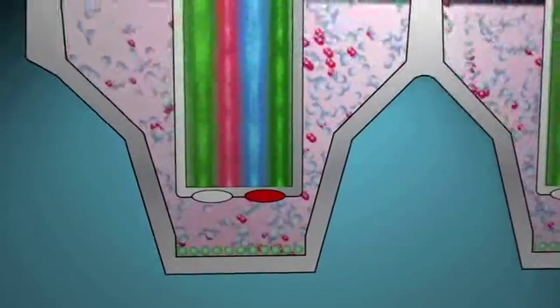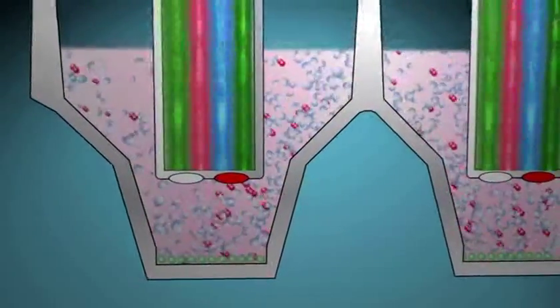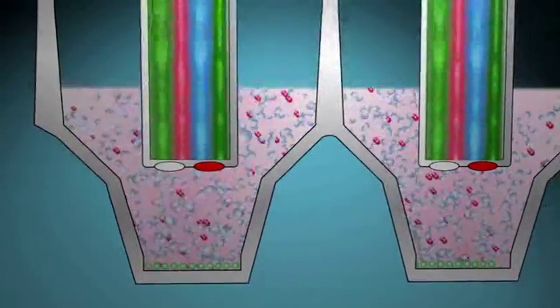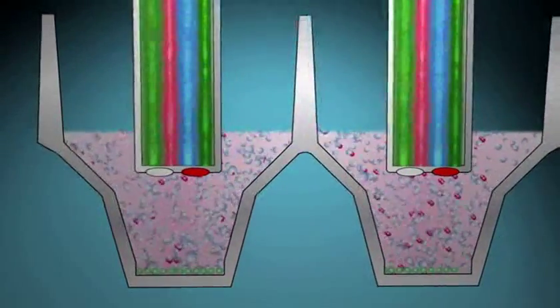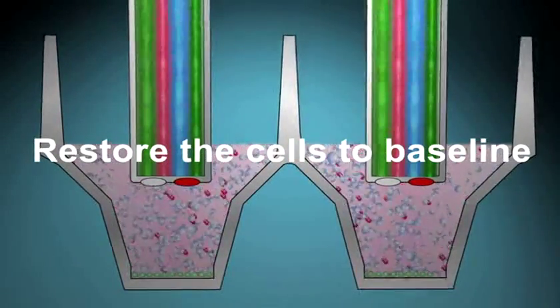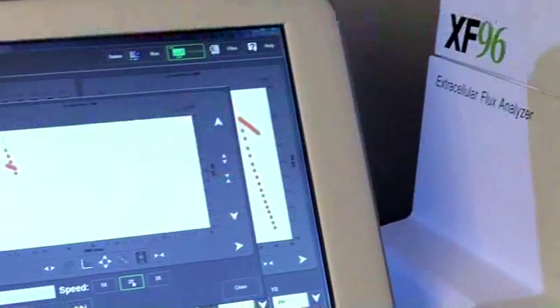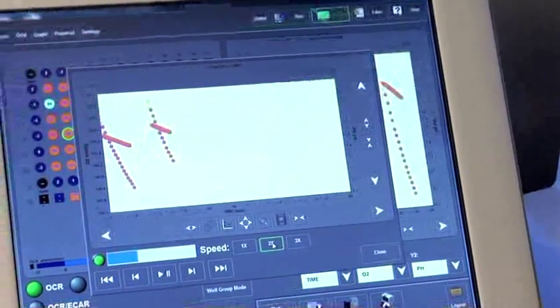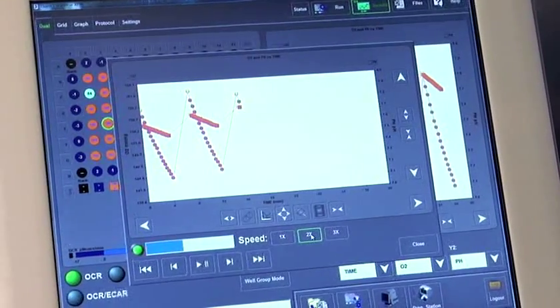When the instrument detects a 10% drop in oxygen or a similar change in proton concentration, the sensor cartridge rises, allowing the medium to restore the cells to baseline. This is how we can make repetitive measurements to create time-resolved kinetic data for each well.